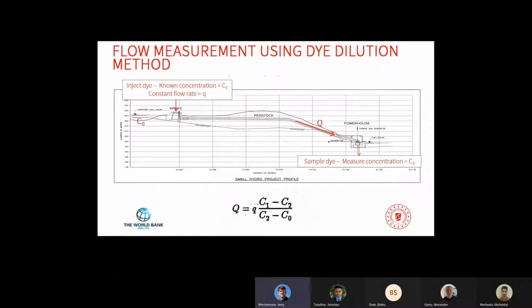So now I'm just going to spend a little more time on the dye dilution method, since that was the primary method that we used to calibrate these DP systems. For those of you who aren't aware, the acoustic flow measurement system is an absolute method of flow measurement, as they call it. So you do not need to calibrate an acoustic flow measurement system.